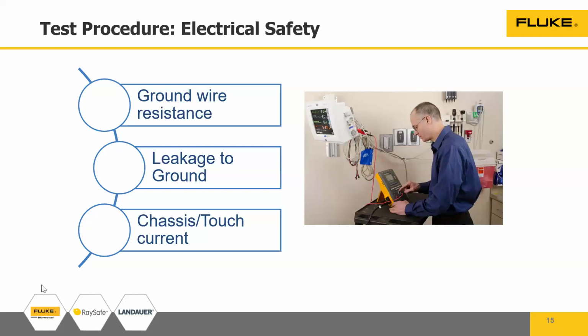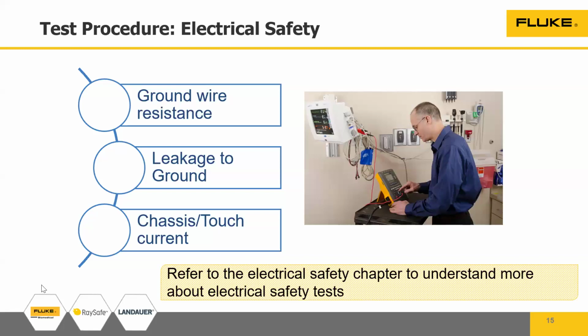As you know, it can have capacitance. Human bodies are highly conductive, and inside the machines there are conductive parts. So it's like a capacitor: a conductor and insulation, so it's like a capacitance. Ultimately, when you touch a medical device, there can be capacitive current. Again, IEC has given a guideline on what kind of chassis or touch current is allowed. We have a detailed safety chapter on this, which you can refer to on our website.